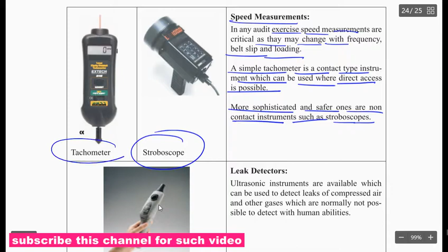Leak detector. Ultrasonic instruments are available which can be used to detect leaks of compressed air and other gases, which are normally not possible to detect with human abilities. And lux meter. Illumination levels are measured with the lux meter. It consists of a photocell which senses the light output and converts it to electrical impulses which are calibrated as lux, that is luminous. So these are the questions related to energy management and audit.